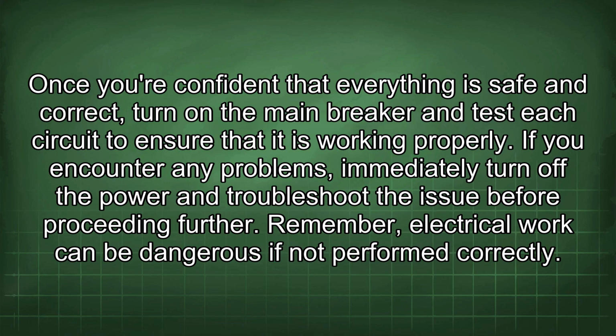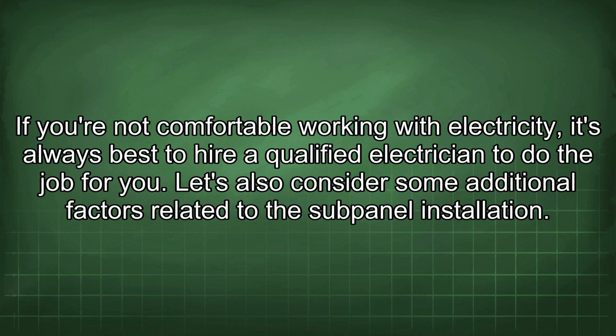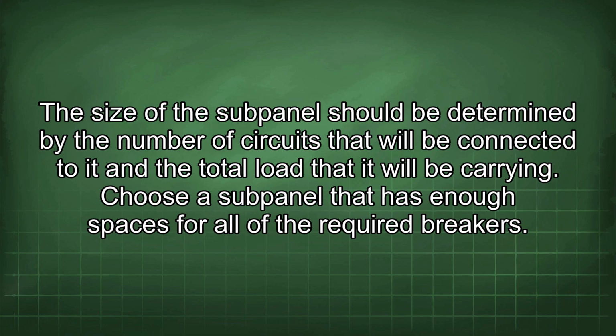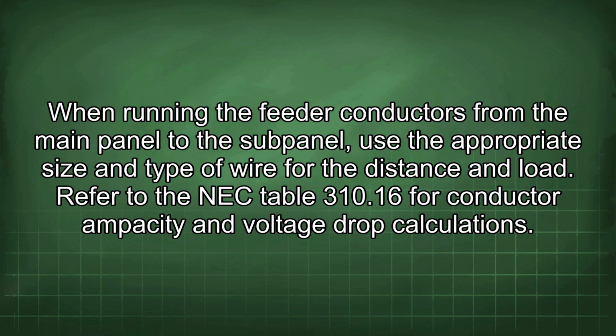Remember, electrical work can be dangerous if not performed correctly. If you're not comfortable working with electricity, it's always best to hire a qualified electrician to do the job for you. Let's also consider some additional factors related to the subpanel installation. The size of the subpanel should be determined by the number of circuits that will be connected to it and the total load that it will be carrying. Choose a subpanel that has enough spaces for all of the required breakers. When running the feeder conductors from the main panel to the subpanel, use the appropriate size and type of wire for the distance and load.